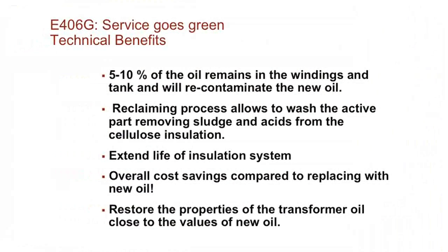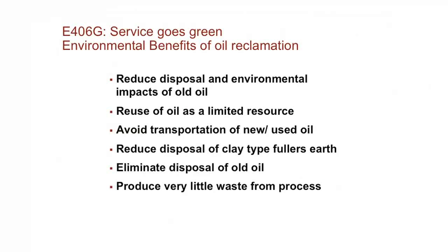There is an overall cost savings if you compare the transportation, the disposal, the logistics, and the downtime, if you are comparing exchange of oil versus online reclamation. So you have the switching time, the de-energized time, and the loss of revenue that you could also consider in that total cost calculation. And as I said, you restore the oil back to its original parameters. Again, we do a comparison based on the current oil quality in order to provide guaranteed limits on what we can guarantee returning those oil parameters to.